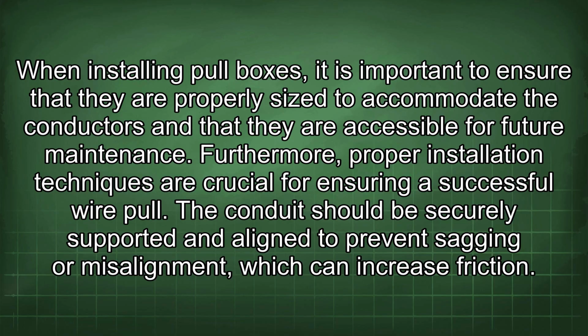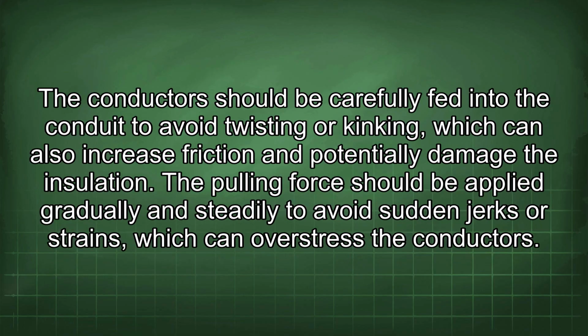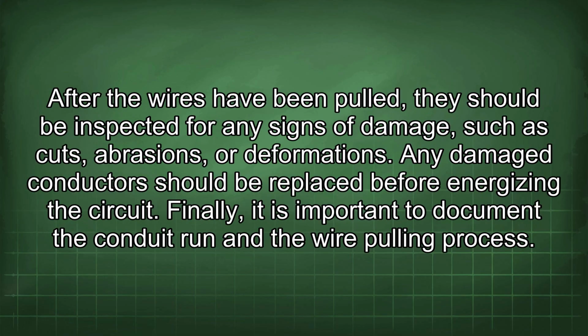Furthermore, proper installation techniques are crucial for ensuring a successful wire pull. The conduit should be securely supported and aligned to prevent sagging or misalignment, which can increase friction. The conductors should be carefully fed into the conduit to avoid twisting or kinking, which can also increase friction and potentially damage the insulation. The pulling force should be applied gradually and steadily to avoid sudden jerks or strains, which can overstress the conductors. After the wires have been pulled, they should be inspected for any signs of damage, such as cuts, abrasions, or deformations. Any damaged conductors should be replaced before energizing the circuit.